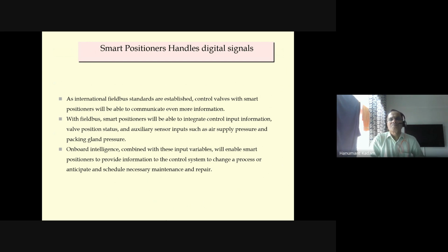Now I'm coming to the digital signal. HART positioners are using analog signal. Fieldbus positioners are using digital signal, purely no analog signal. As the international fieldbus standards are established, control valves with smart positioners will be able to communicate even more information. With fieldbus, the smart positioner will be able to integrate control input information, valve position status, and auxiliary sensor input such as air supply pressure and packing and gland pressures.